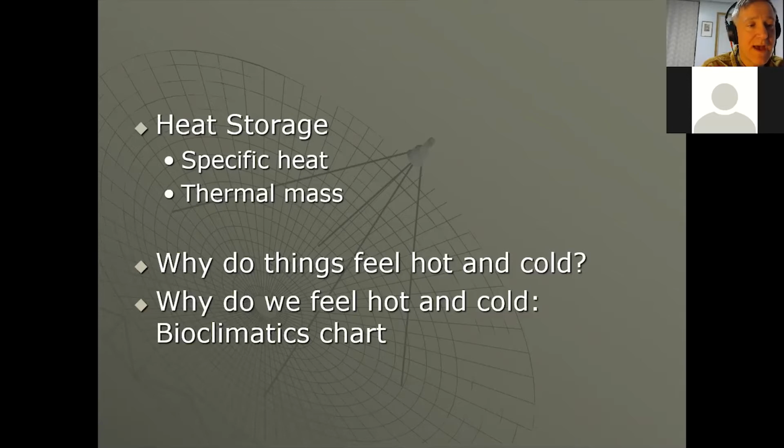And if you do that, you increase the delta T across things. Well, there are other practical problems with that too, but one of them is you have these big high temperature differences. And the bigger the temperature differences, the higher the heat transfer. So as you're trying to move the hot air or cold air to where you need it, you're going to lose or gain heat that you don't want to. So that's why water is a really good way to move energy around.